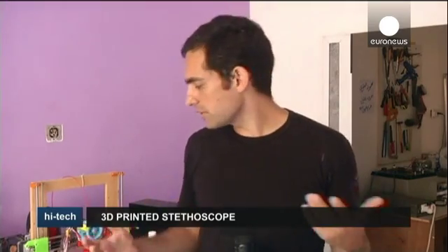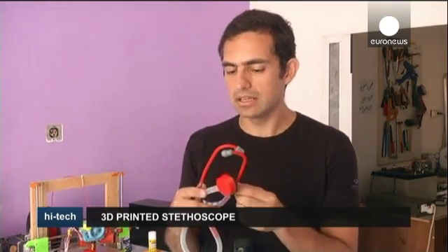I ran into a little toy that my brother's son had been playing with and realized that this toy stethoscope, which must have cost $1 to make, was not terrible. So that's where the idea came from — to have this plastic stethoscope, which is similar to toy stethoscopes in that it's plastic, but is actually engineered so that it is as good as the market leader.